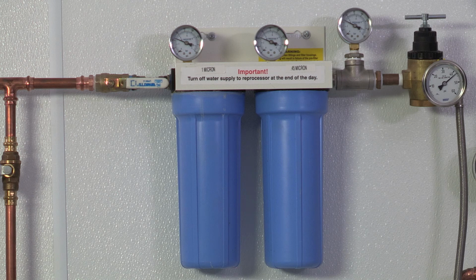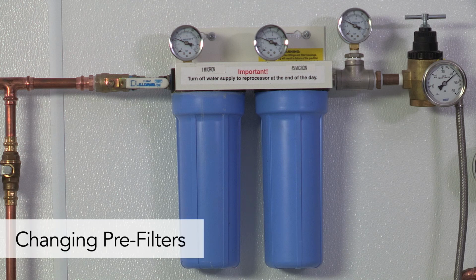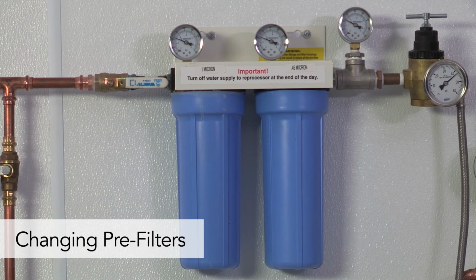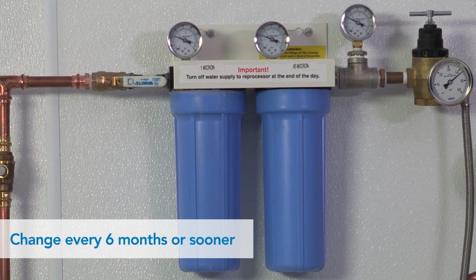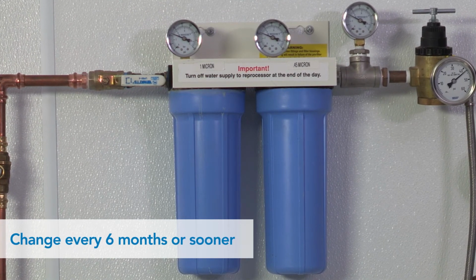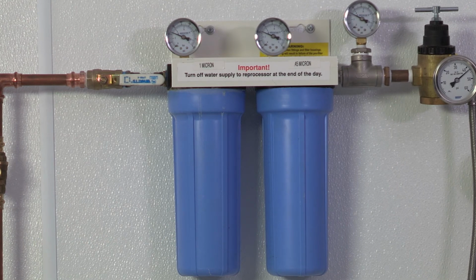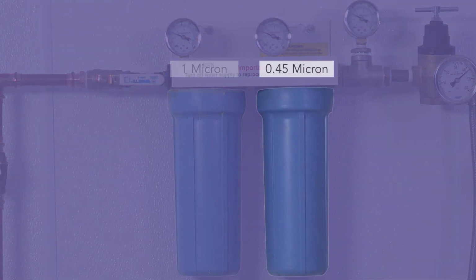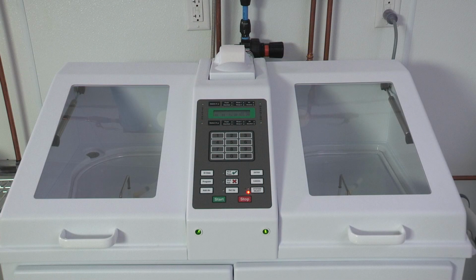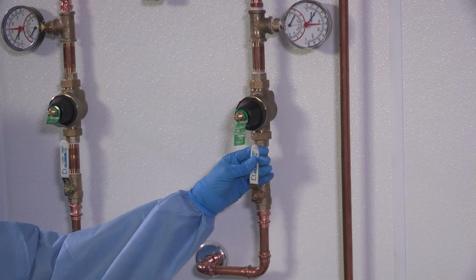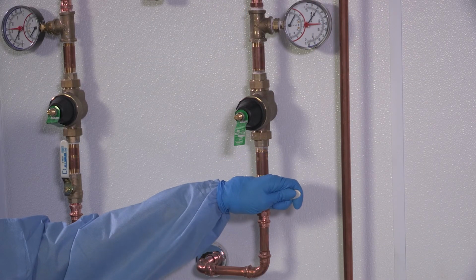The filters mounted outside of the unit are called pre-filters. These filters should be changed every 6 months or sooner, depending on the quality of the incoming water. The incoming water will first encounter the 1 micron filter, then the 0.45 micron filter. To change the pre-filters, ensure the unit is idle and the main incoming water supply valve is closed.